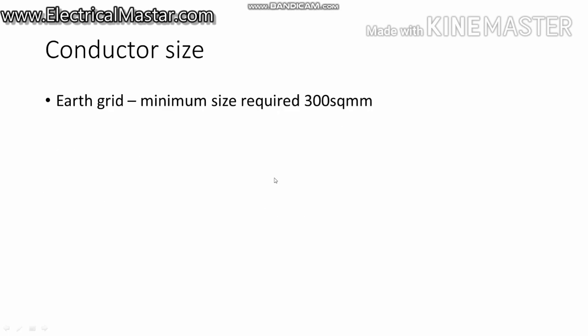And fourth is the conductor size. It is important in the earthing layout, because you should know what cable size is used for which purpose. The first one is the earth grid. I already told you the earth grid is the interconnection between the earth pits. For the minimum cable size you have to use 300 square mm, and it should be bare copper conductor. It is not a sleeve type. So you have to use bare copper conductor, and connect it in underground installation.